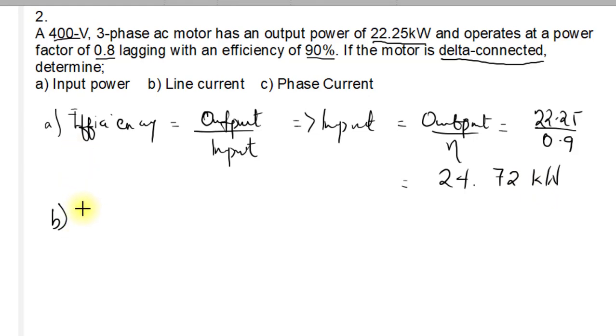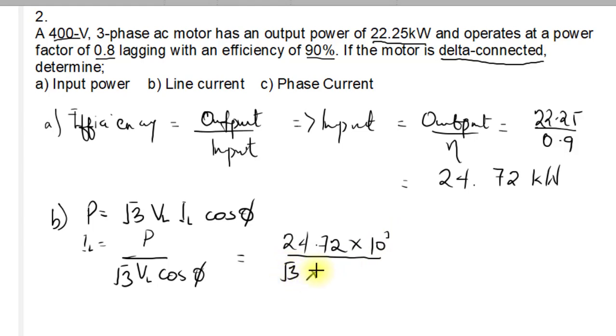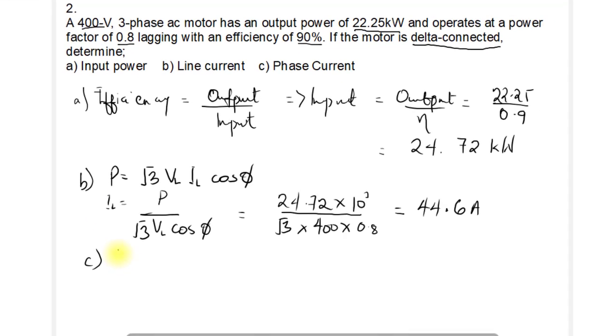To find the line current, we use the formula P = √3 × VL × IL × cosφ. Making IL the subject and substituting, IL = 24.72 × 10³ divided by (√3 × 400 × 0.8), giving us 44.6 amperes. Since the motor is delta connected, IL = √3 × IP, so the phase current IP = 44.6 / √3 = 25.75 amperes.